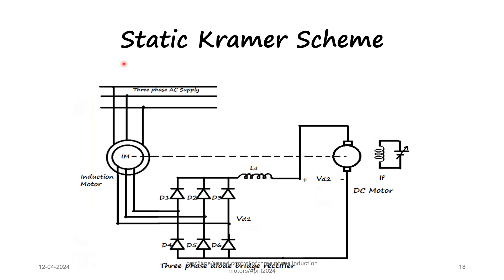The static Kramer scheme converts the rotor slip power to DC using a diode bridge. This DC power is fed to a DC motor which is mechanically coupled with the induction motor, and speed control is done by varying the field current of the DC motor. For large speed range applications, the diode bridge is replaced by a thyristor bridge and speed is controlled by varying the firing angle of the bridge. The speed in that case can be controlled up to the standstill condition.